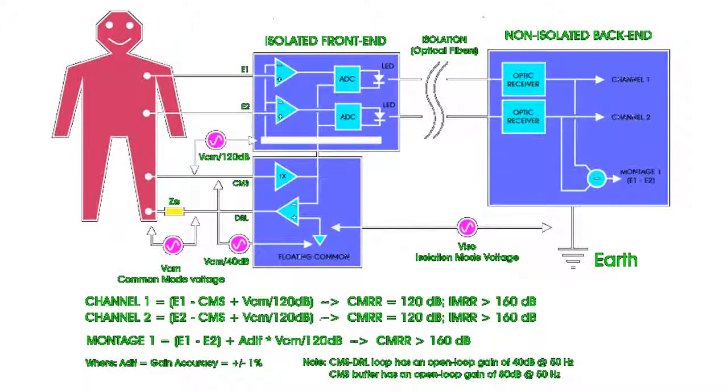These techniques relate to the ability of an amplifier to reject the effect of voltage applied to both input terminals simultaneously. The CMR ratio, CMRR, is the ratio in decibels of the differential voltage amplification to CMV amplification. CMRR is often defined at an associated effective frequency with a maximum allowable input imbalance, such as 120 dB at 500 Hz, 1000 ohms.